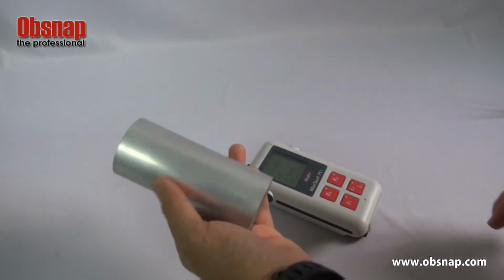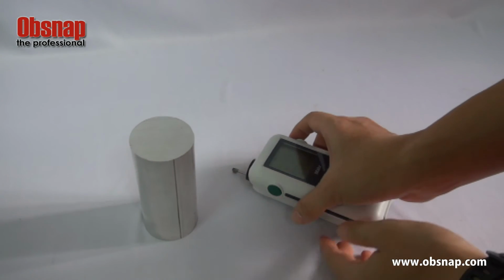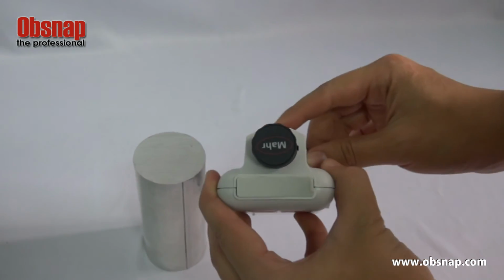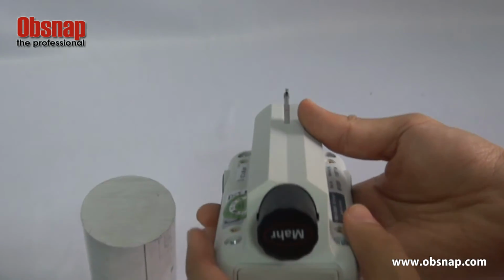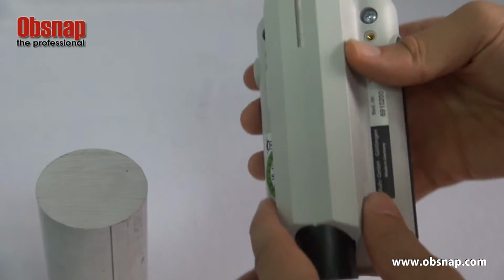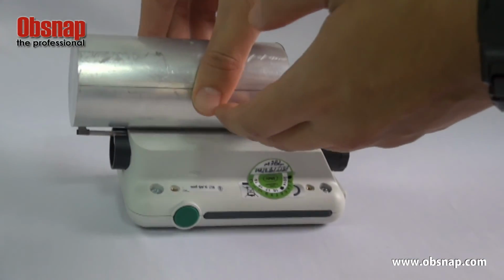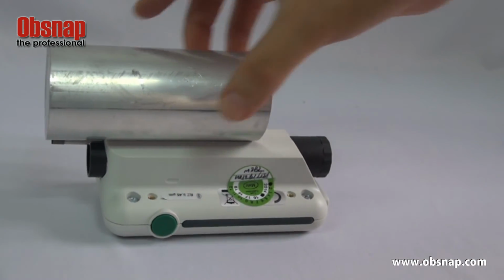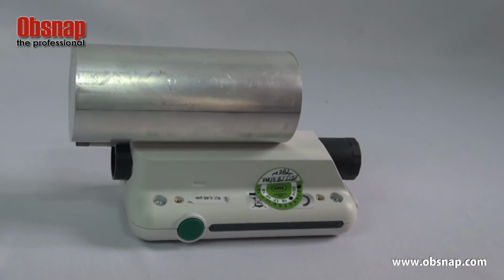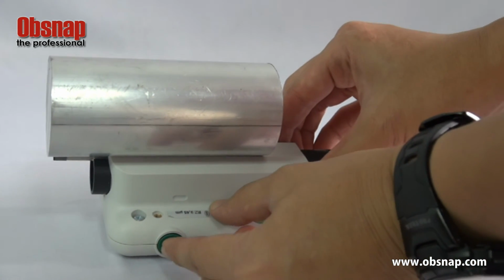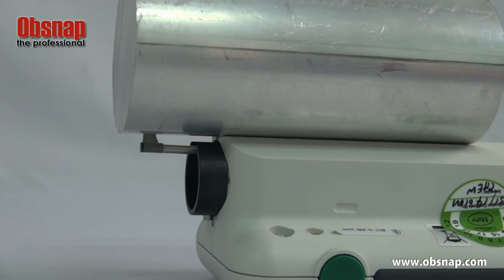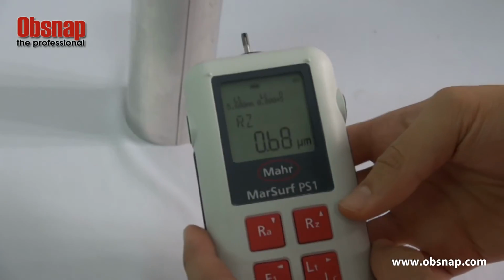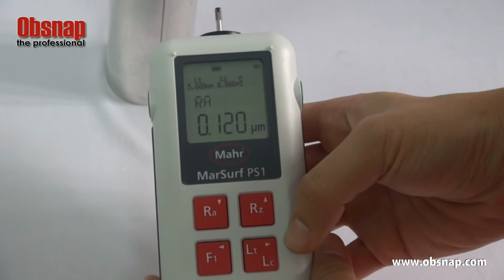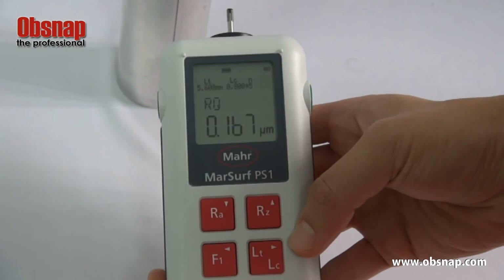So to measure a cylinder part like this, the device is designed for that as well. There's a V block at the bottom here to fit a cylinder part like that, so you don't have to find a center point from up here. So just lay it flat on the table and put the part on top of it. It will fit into the V block in its center position. And now you just press the green button at the side to start it. This is the RZ result and the RA result. The F1 is RQ. This is the result.